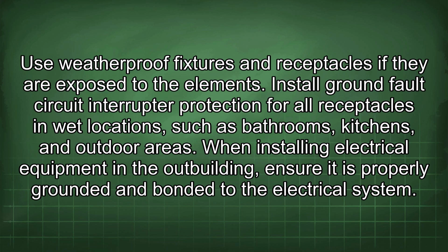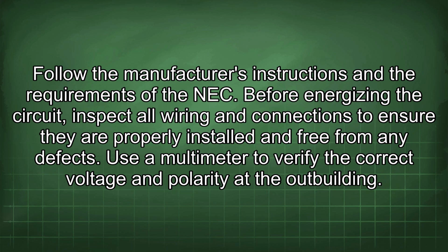Install ground fault circuit interrupter protection for all receptacles in wet locations, such as bathrooms, kitchens, and outdoor areas. When installing electrical equipment in the outbuilding, ensure it is properly grounded and bonded to the electrical system. Follow the manufacturer's instructions and the requirements of the NEC.